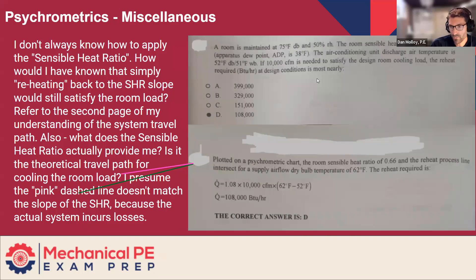So I think that alone is a little bit confusing because from my perspective, everything should be in the unit. So you have to be really clear that this is the discharge air temperature off the coil, cooling coil, which is cooling the air and stripping it of moisture. And then it's going to go over a heating coil, which is downstream of the cooling coil to perform this reheat. And I guess the way they're performing this, it's not totally clear in the problem statement, but it's doing that cooling process, cooling and drying. And then as a second step, it's getting the reheat. And maybe that's a later step in the same unit. Maybe it's a separate unit. Not totally clear, but what we can say for sure is that there is reheat.